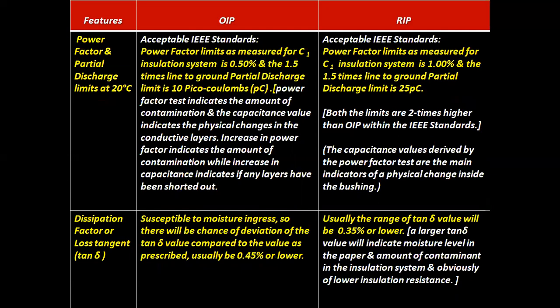Power factor and partial discharge limits at 20 degrees centigrade. Acceptable IEEE standards: the power factor limit as measured for the C1 insulation system is 0.50%, and the 1.5 times line to ground partial discharge limit is 10 picocoulombs. Power factor test indicates the amount of contamination, and the capacitance value indicates physical changes in the conductive layers. An increase in power factor indicates the amount of contamination, while an increase in capacitance indicates if any layers have been shorted out.